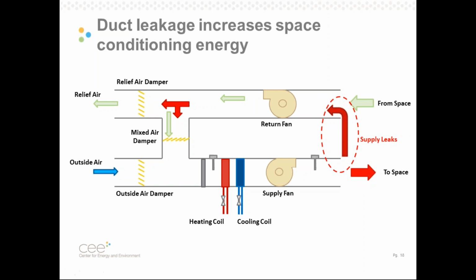The air has not provided ventilation. It hasn't provided heat or cooling. It's short-circuited the building effectively. And then it passes through the return fan. Lost my little cursor here. There you go. And at some point, we exhaust a fraction of that air that we conditioned, we moved out the building without it doing anything for us. And the thermal energy we used to condition that air is now lost to us.